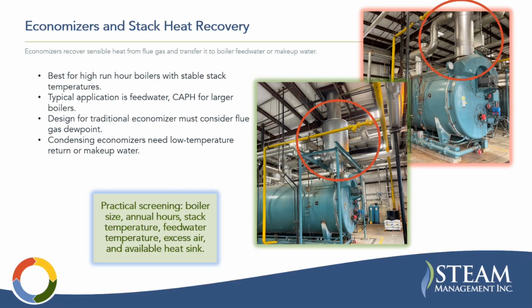Another interesting scope, which I would like to see somebody do, is to duct the inlet of your combustion air up to the top of the boiler room, where the heat is stratified up there, and pull that into the boiler for a hotter combustion air intake. I think that's an interesting and simple scope.